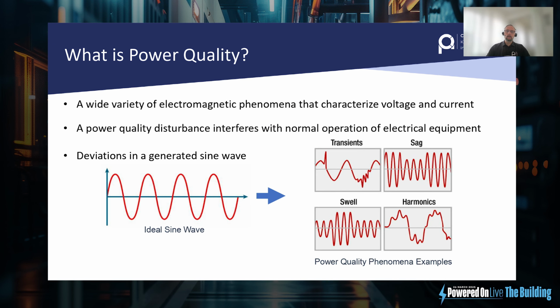So, what is power quality? Forgive me, I don't know the audience here today. If some of this goes over your head or you want to talk about any of it offline, I'm more than happy to arrange conversations and Teams calls with anyone to learn more. But ultimately, what we're looking at is whether the signal coming into your equipment is clean. Does it look like a sine wave, which you can see there on the left-hand side, the ideal sine wave? And quite often it's not, and quite often you don't know that it's not. You can get transients, which are high frequency spikes in the mains. You can get sags and swells, where the voltage reduces and increases, and harmonics, which are a distortion of the waveform away from a sine wave.